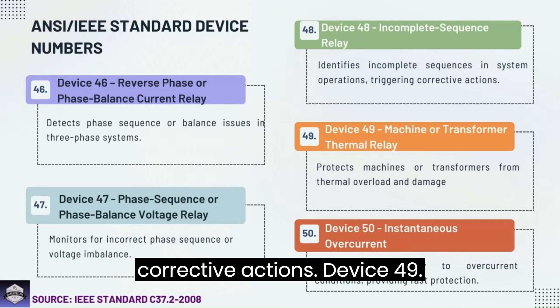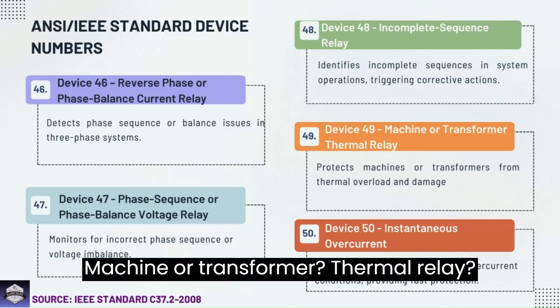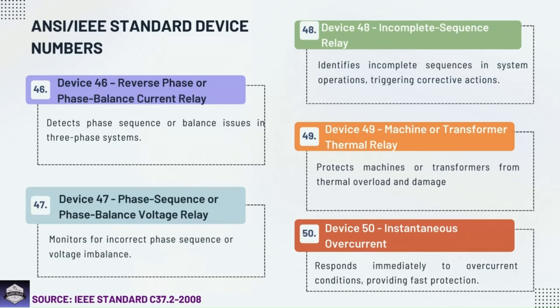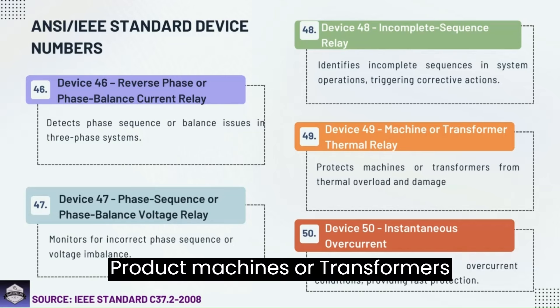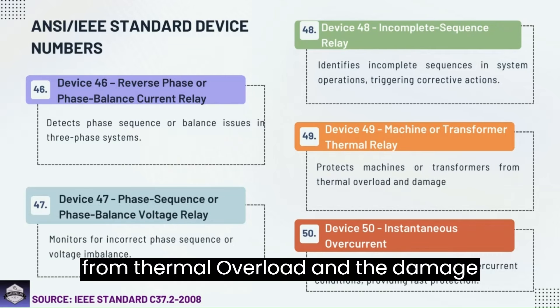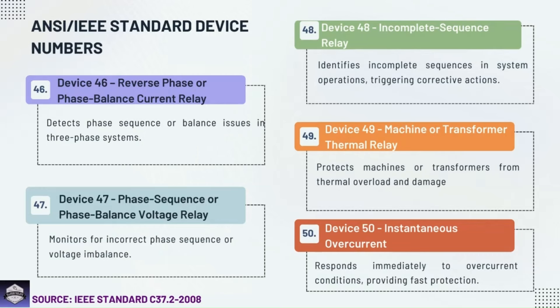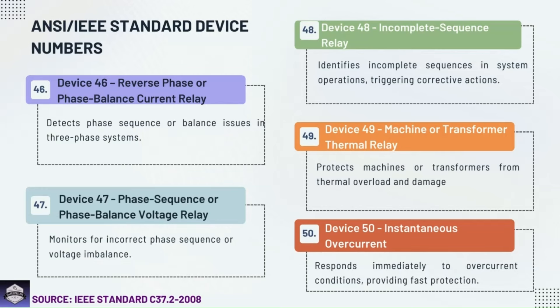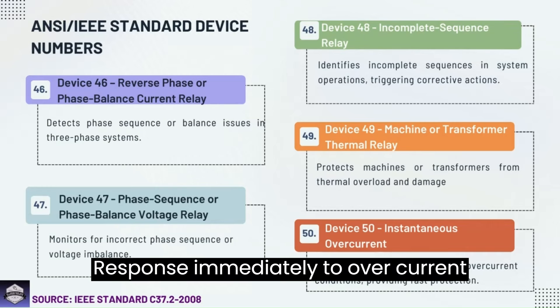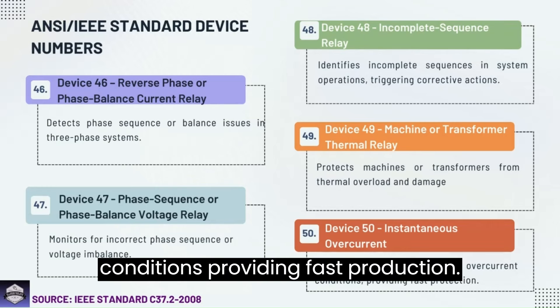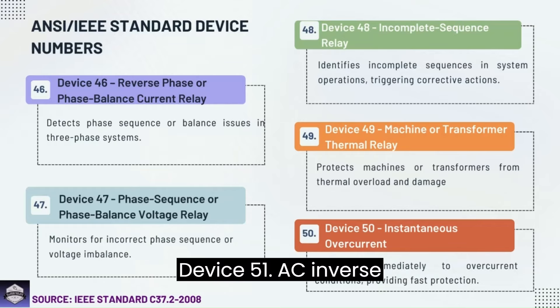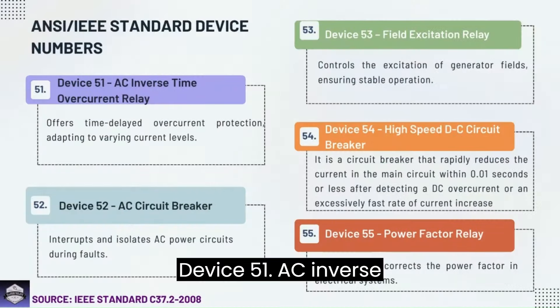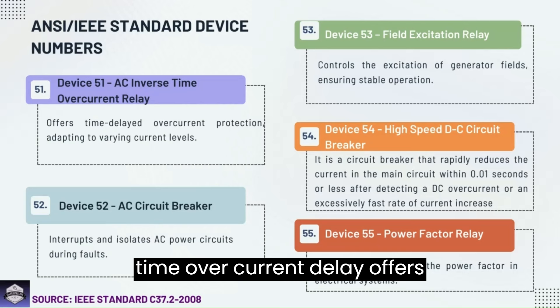Device 49: Machine or transformer thermal relay — protects machines or transformers from thermal overload and damage. Device 50: Instantaneous overcurrent relay — responds immediately to overcurrent conditions, providing fast protection. Device 51: AC inverse time overcurrent relay — offers time-delayed overcurrent protection, adapting to varying current levels.